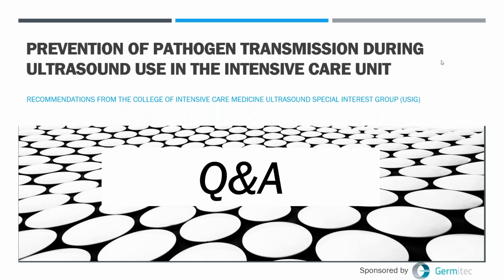Thank you. This next question, Westerway and Basil found the cable of the probes to be highly contaminated. Does the group recommend products that are only capable of disinfecting the entire device to the correct level, not just the handle and probe distal end? No, it includes cables as well. I didn't include it in my talk, but we absolutely include cables. The thing is that we can never get full clearance as to, if the cables wear out and they become contaminated, they'll simply just have to be replaced. But yes, anything that's high frequency, that would include cables, of course.